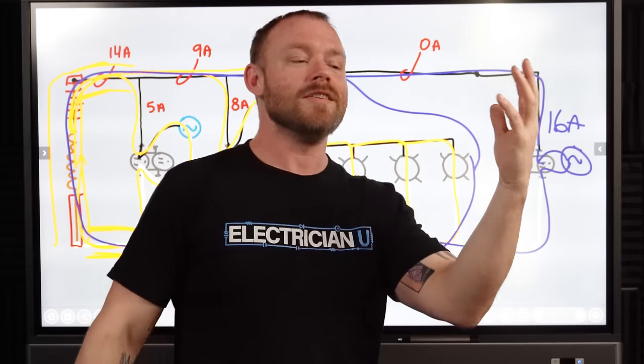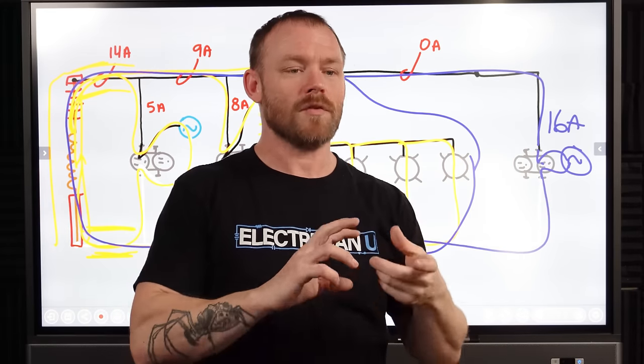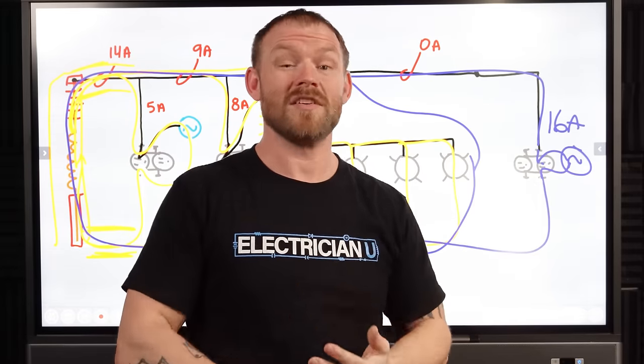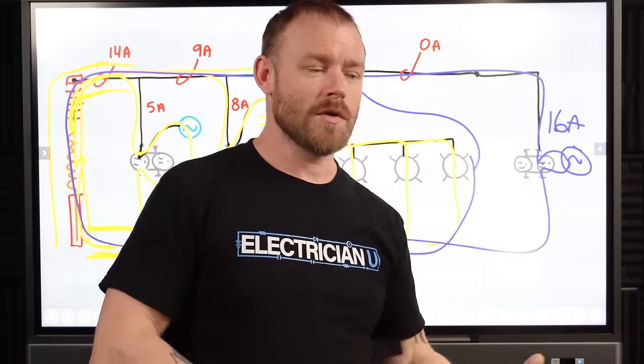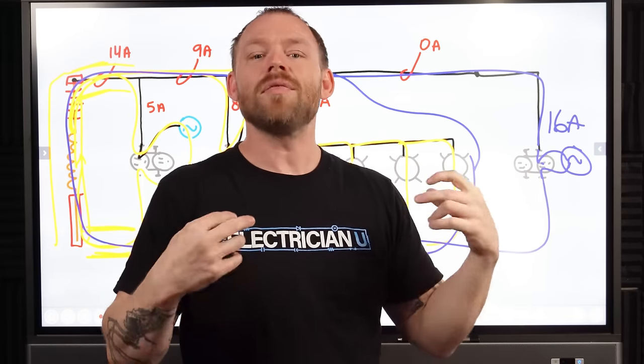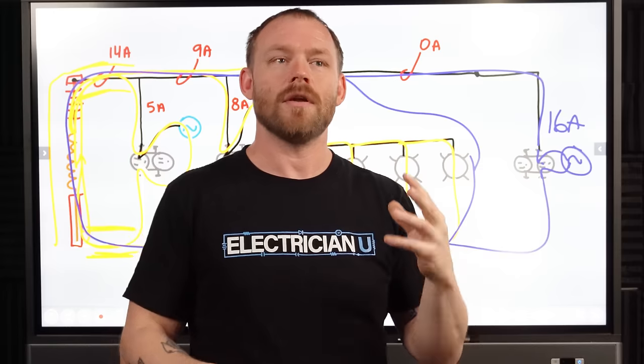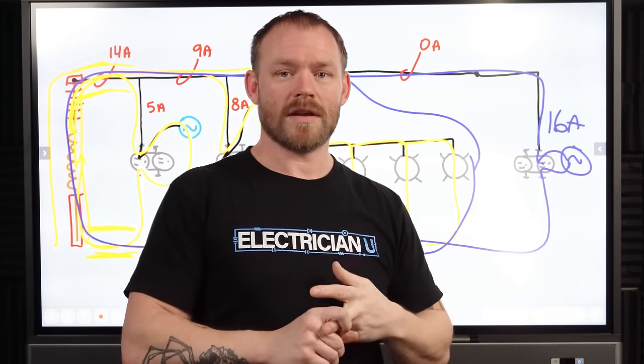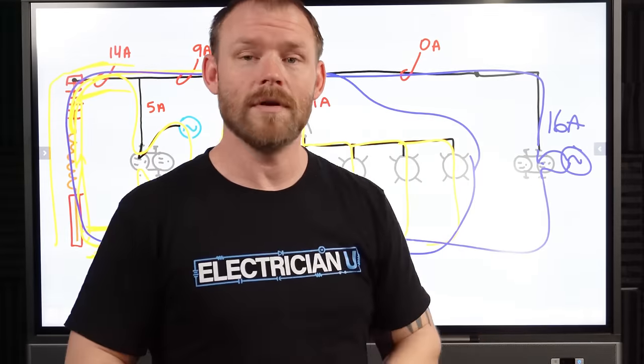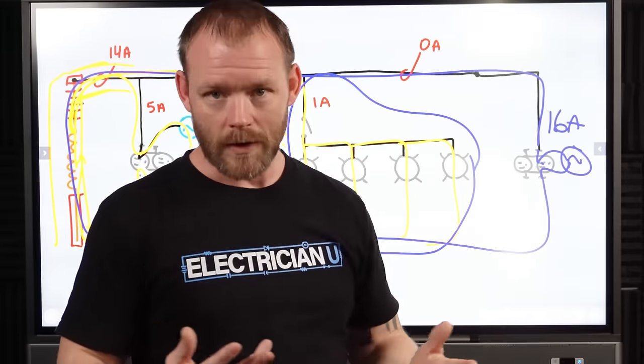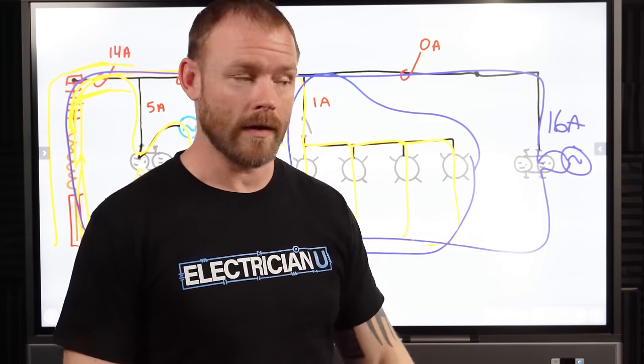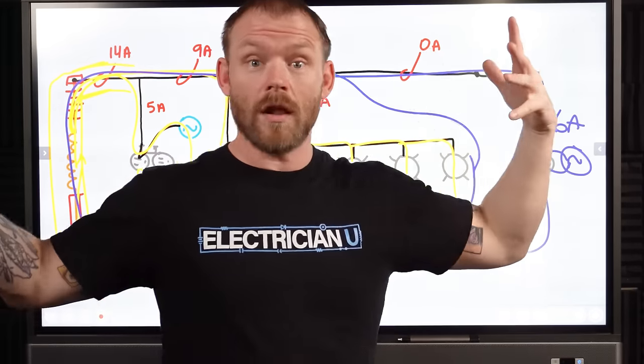You could add 40 LED lights and maybe get one or two amps, which shows you can use smaller conductors. But you have to make sure you're using the right rated equipment — the right conductors — that your inspector will actually pass. Don't run Ethernet cable to power lights; it's just not rated for that use. But in theory, if you have insulation that can handle it, conductor size you can hook up to a breaker, and you're using listed and rated equipment, you could use smaller conductors like 16, 18, or 20 AWG because the load is so small.